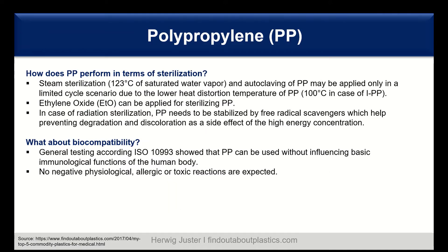How does polypropylene perform in terms of sterilization? Steam sterilization and autoclaving of polypropylene may be applied, but only in a limited cycle scenario due to its lower heat distortion temperature of around 100°C. Ethylene oxide can be applied for sterilization without any problem. When using radiation sterilization, PP needs to be stabilized by free radical scavengers — additives that prevent degradation and discoloration.